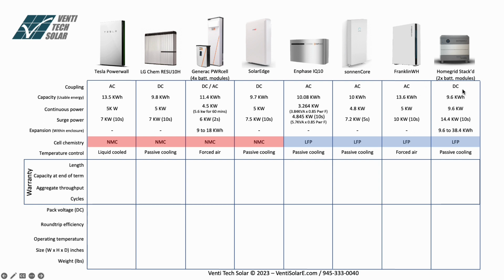The Home Grid is definitely DC. There are no inverters on that solution. There is not even a DC to DC conversion. This AC in here has a built-in inverter. The Generac could be AC or DC because this little box over here is actually an inverter. The system can use just the battery enclosure and a certified other inverter. And the LG Chem doesn't have any inverters. Tesla has built-in inverters and power converters inside that box, so it's definitely AC.